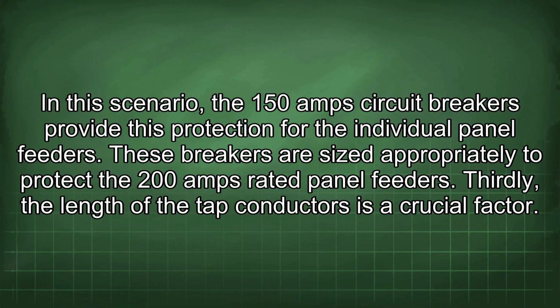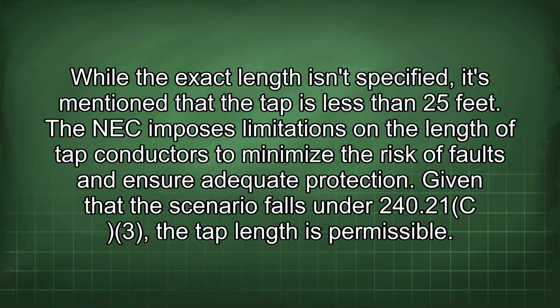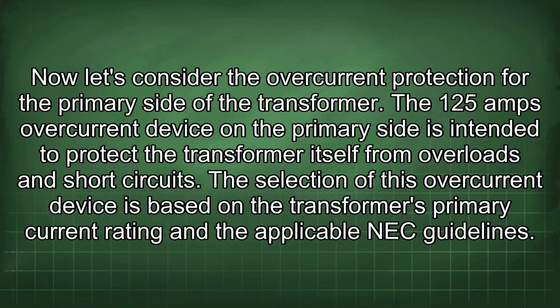Thirdly, the length of the tap conductors is a crucial factor. While the exact length isn't specified, it's mentioned that the tap is less than 25 feet. The NEC imposes limitations on the length of tap conductors to minimize the risk of faults and ensure adequate protection. Given that the scenario falls under 240.21(C)(3), the tap length is permissible. Now let's consider the overcurrent protection for the primary side of the transformer. The 125 amp overcurrent device on the primary side is intended to protect the transformer itself from overloads and short circuits.